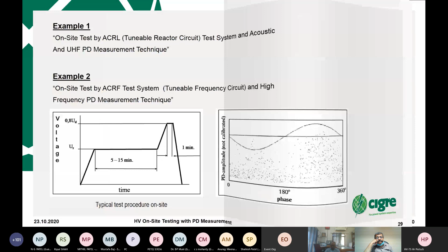Now I would like to come to the cable, which was mentioned in the introduction. So this brochure shows 5 examples, different wave shapes or voltage sources for medium voltage cables, lower voltage cables and high voltage cables. With a conventional one, with the resonant test frequency, it's damped AC for diagnostic PD measurement technique. And then for extruded extra high voltage cable with a resonant test system, and the very low frequency, which is allowed for commissioning as a withstand test, and of course for all PD diagnostic techniques. And again, an example is shown in this brochure about PD with UHF technology for special cable accessories, mainly joints.